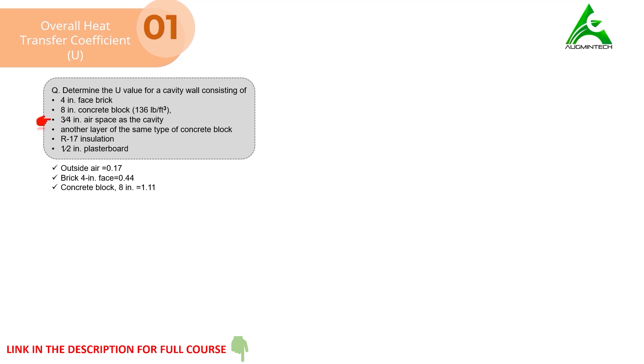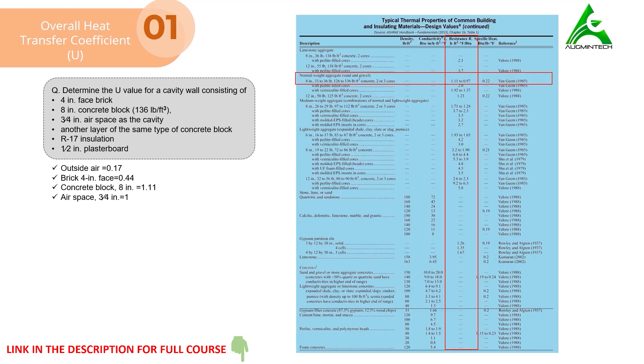Then we find the resistance of the 3/4-inch air space cavity. This value is very close to 1 always, so for air spaces the resistance is chosen as 1. Again, we use the same chart to get the resistance for another layer of the same type of concrete block, which is the same as the 8-inch concrete block, so we use the same value of 1.11.